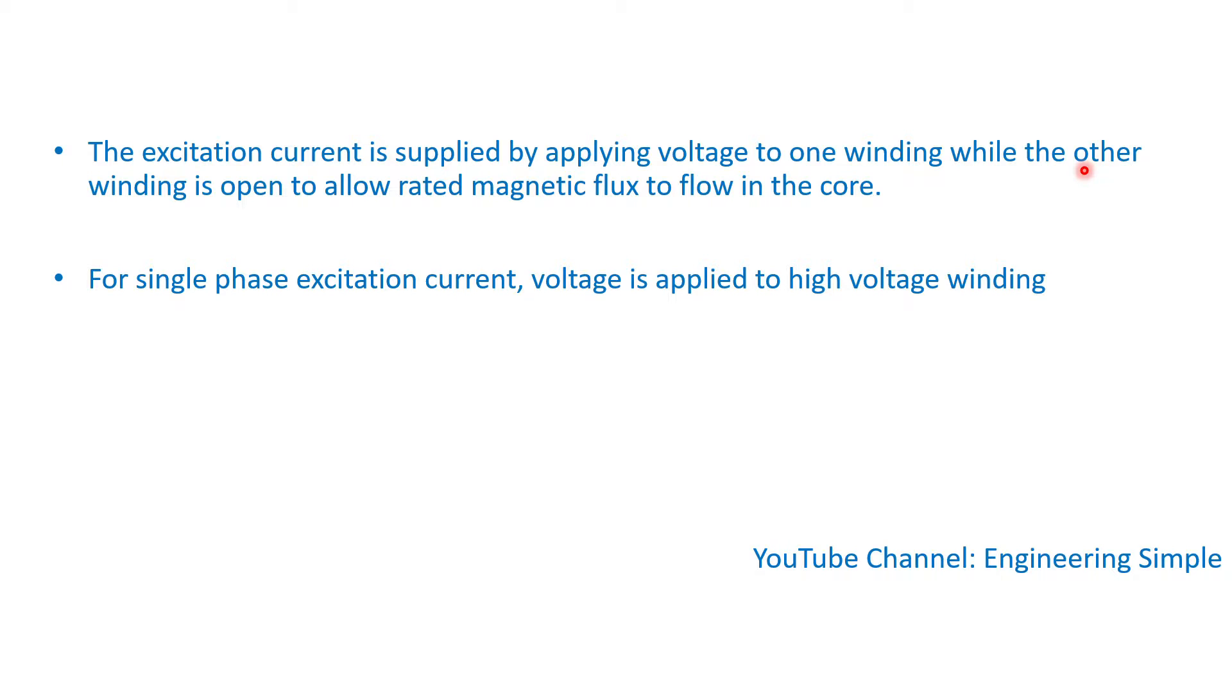For single phase excitation current, voltage is applied to high voltage winding. For three phase excitation current, voltage is applied to the low side, and the reason being is because the low side has lowest voltage.